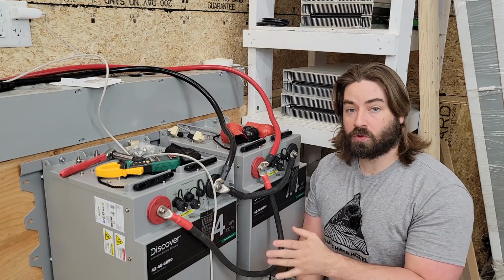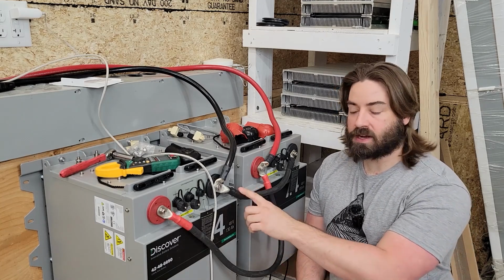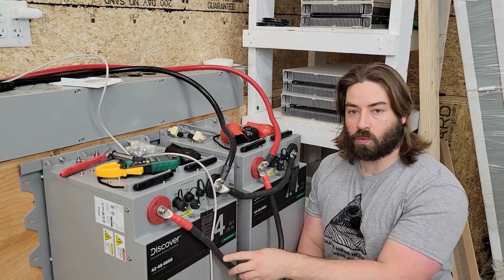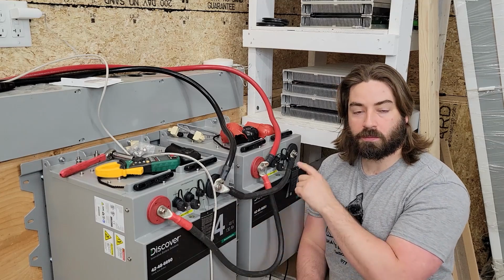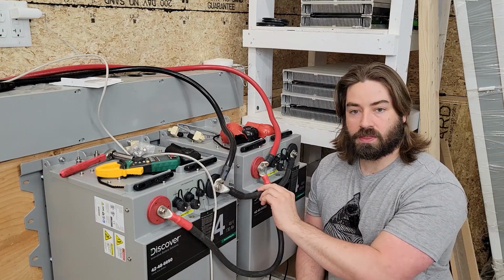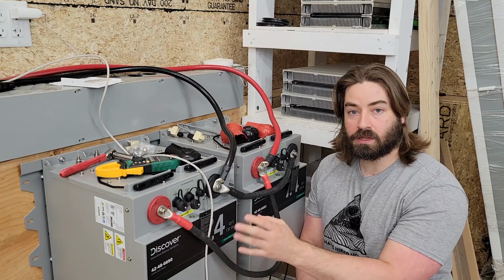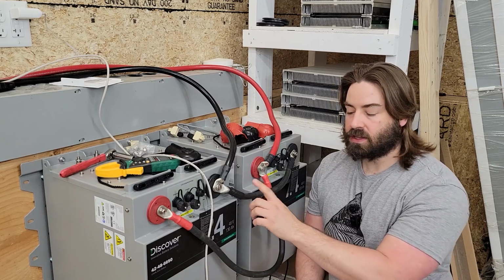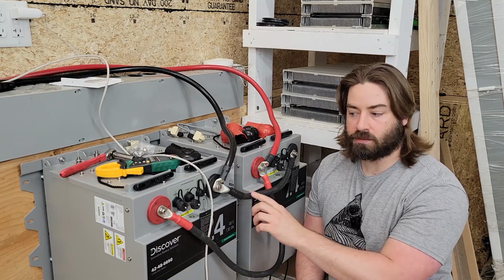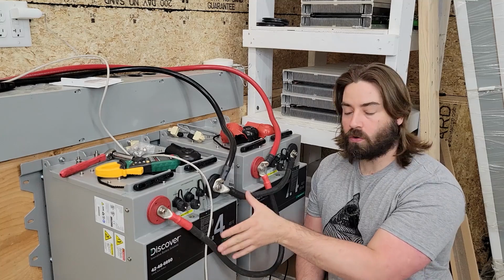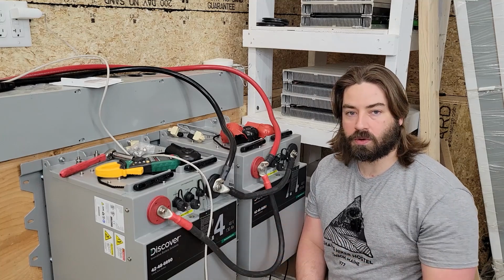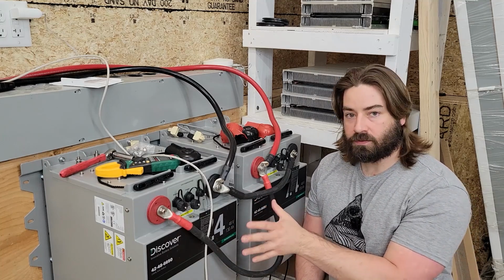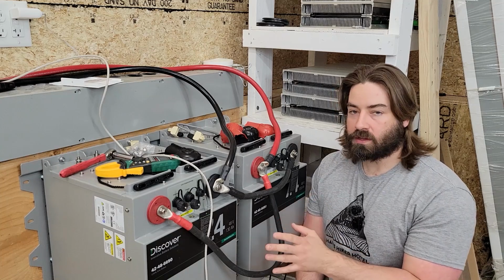I should note I'm doing one thing against the manual: I'm daisy chaining these with different length wires. When you daisy chain multiple batteries together, you want these jumper wires to be the same length or the same resistance. In this case, the negative is a little bit shorter than the positive. They're 4-aught wires, so we're probably not going to notice the amperage difference between them, but I wanted to point that out.